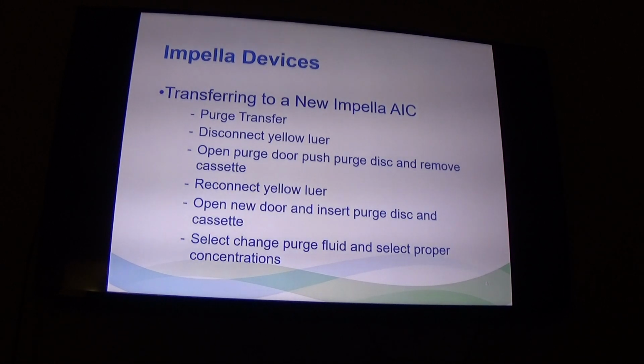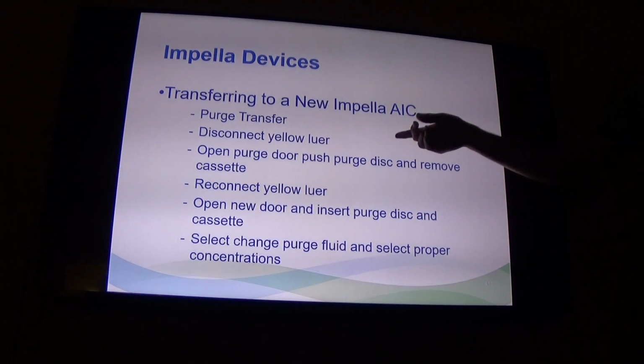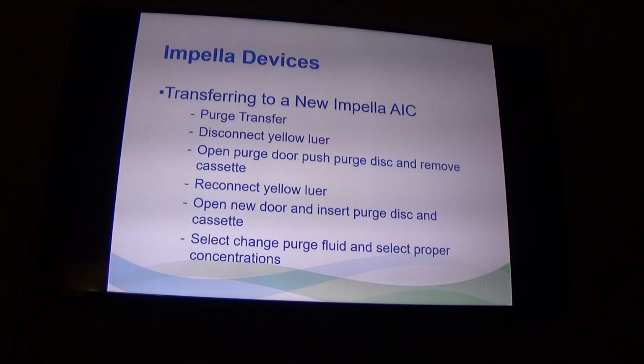So transferring the purge solution, you disconnect that same yellow luer lock, open the purge door, push the purge disc and remove the cassette. Reconnect the yellow luer lock onto the new one, open the purge door, insert the cassette, select change purge fluid and select the proper concentration. It's usually D5 and it's usually already pre-programmed in. And again, the device will pretty much walk you through it. If the device isn't walking you through it well enough, there's a manual that comes with it, on the cart with the device.